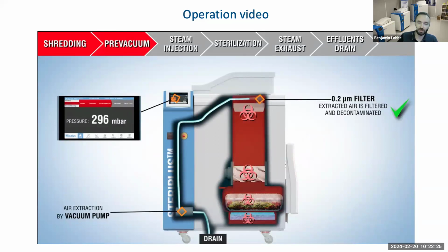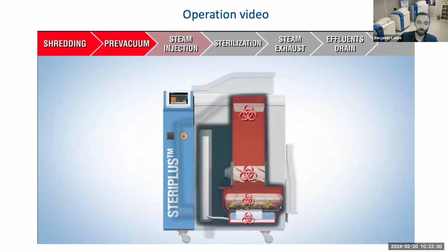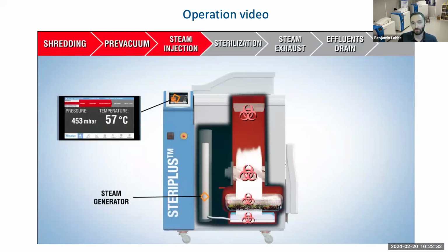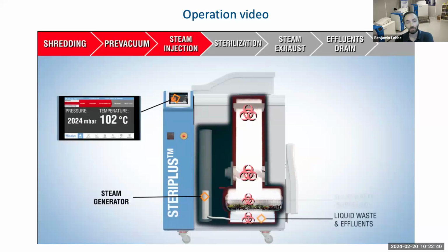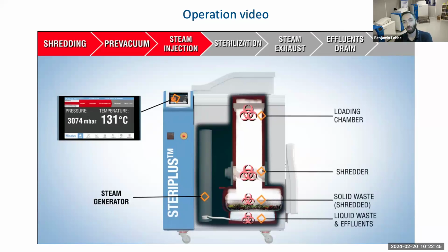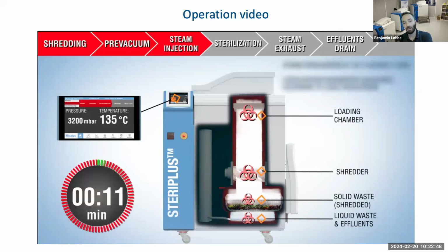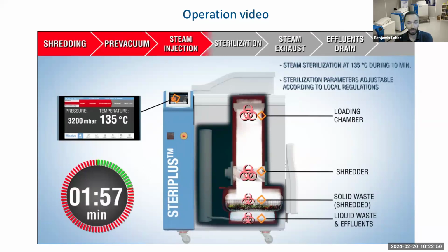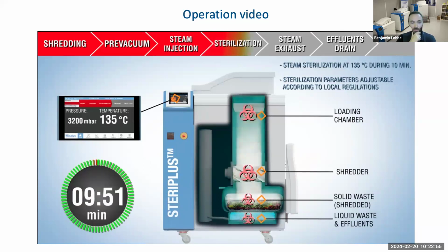Once the shredding process is done, we will start to sterilize the waste, of course, but also the full unit. So everything will be sterilized by steam. As in a basic autoclave, we will reach about 135 degrees during 10 minutes. The steam will penetrate the waste, but will also be in contact with the shredder, the pusher, and the loading chamber. So even for maintenance operations that I will detail later on, everything is sterilized and everything is safe inside the unit. Once we reach the 10 minutes of decontamination, the steam is exhausted.